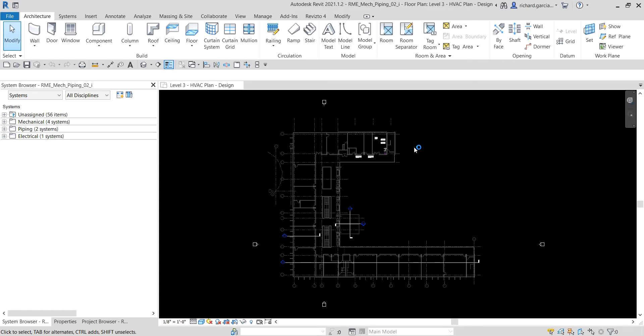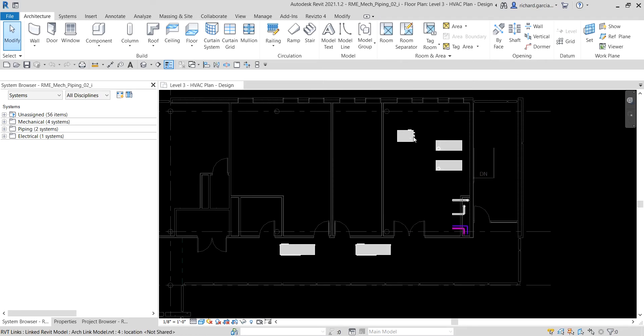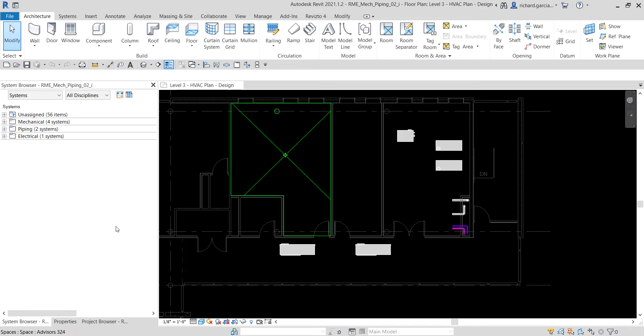The recommended workflow to create the piping system is: first, place mechanical equipment and other system components, which we already did last video. Then we are going to create a logical connection between the system components, which is what we are doing in this video. Finally, we will create pipes to physically connect the system components. An important note: all system components are logically connected either by a system that you create or by a default system. Unlike logical connections, physical connections like pipes are not required for system creation. You can create pipes to connect system components, but without a corresponding system, analysis cannot be performed.